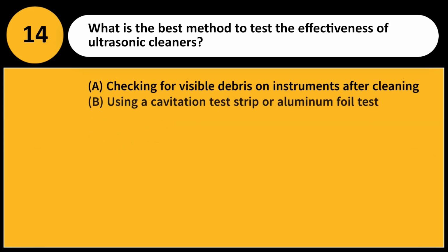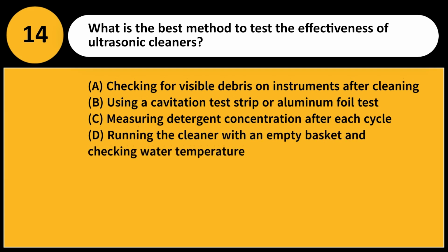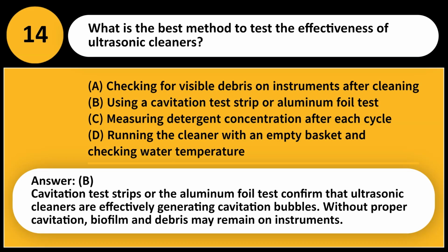What is the best method to test the effectiveness of ultrasonic cleaners? A. Checking for visible debris on instruments after cleaning. B. Using a cavitation test strip or aluminum foil test. C. Measuring detergent concentration after each cycle. D. Running the cleaner with an empty basket and checking water temperature. Answer: B. Cavitation test strips or the aluminum foil test confirm that ultrasonic cleaners are effectively generating cavitation bubbles. Without proper cavitation, biofilm and debris may remain on instruments.